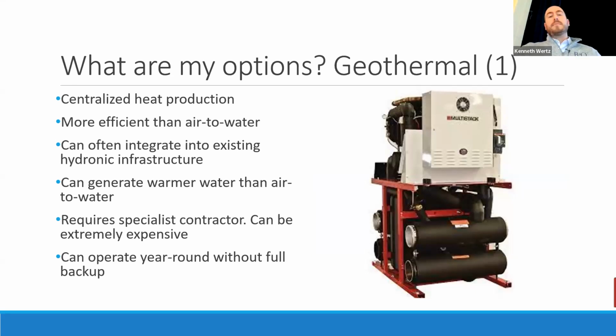So again, if we're looking at trying to distribute hot or cold water throughout a building, there's the air to water option where you've got a condenser outside. The other option is geothermal. So there's two different flavors of geothermal. The first one I'll talk about is sort of the centralized option where you've got the equivalent of a chiller or a boiler that's being fed by the geothermal field. And it's distributing hot and chilled water throughout the building.